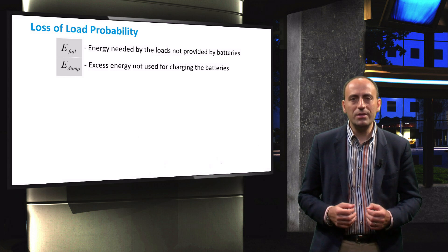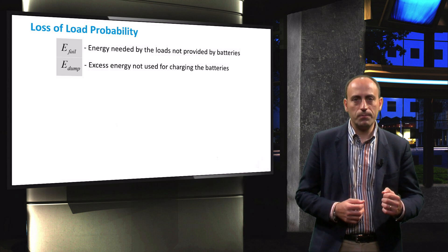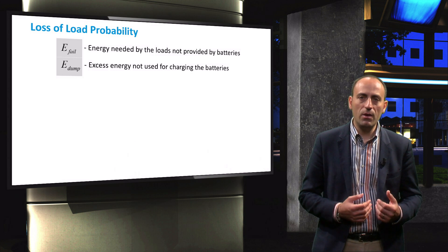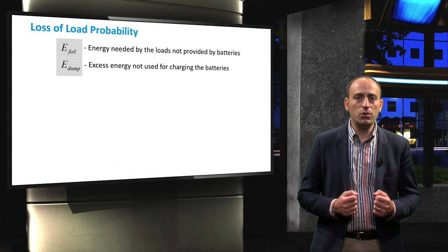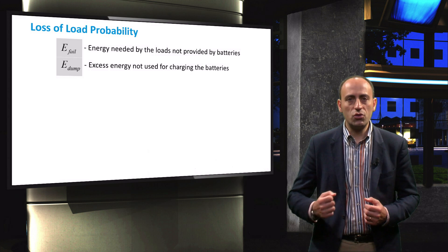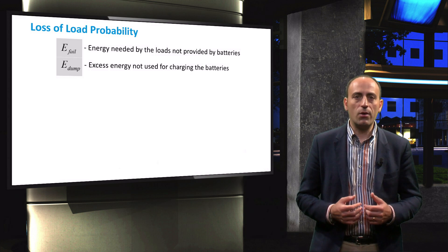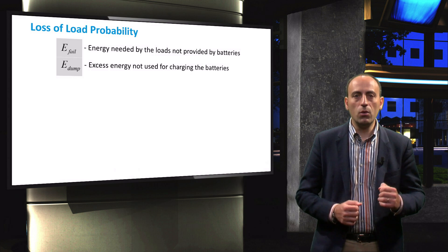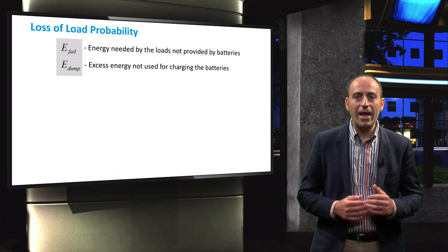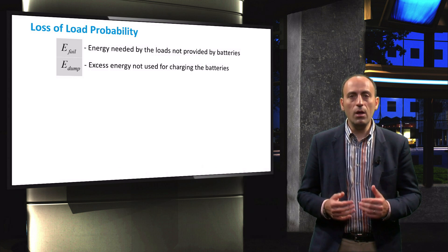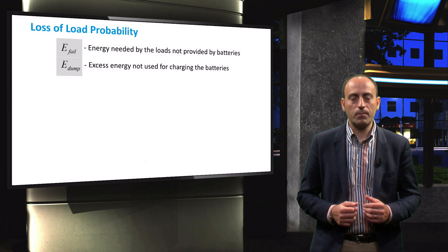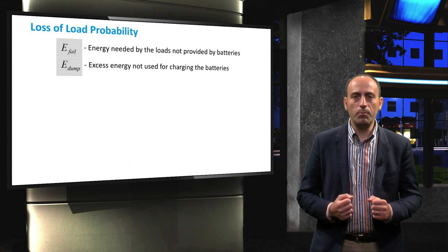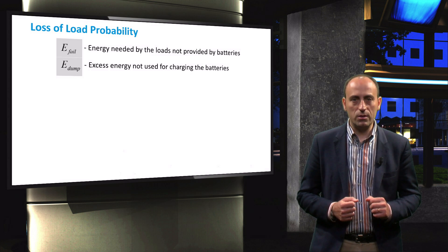The second parameter is E-dump. E-dump is defined as the energy produced by the PV array that is neither used to power a load nor stored in the batteries. This can occur, for example, if the PV generation is greater than the load consumption and the batteries are already full after a number of sunny days. It therefore basically represents the overproduction of the PV array in your PV system.